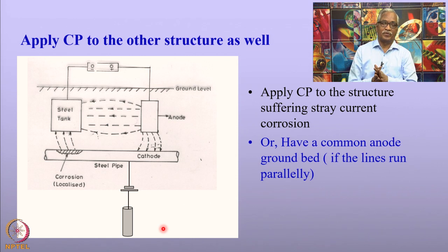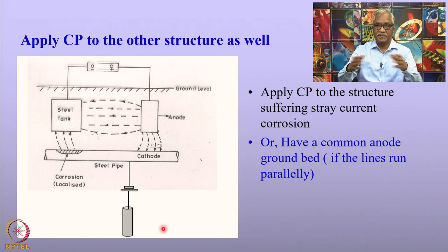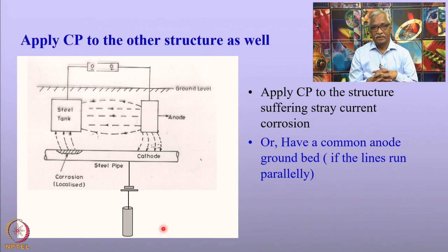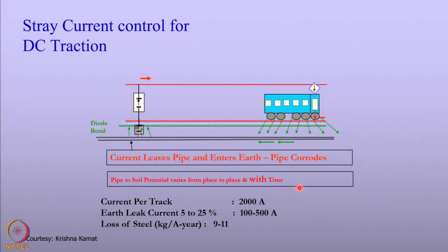Another effective way of controlling stray current corrosion is to relocate the anode ground bed. If pipelines are traveling parallel to each other, it is possible to relocate the anode ground bed far away from the intended pipelines, making the stray current entering the foreign line minimal. We have seen earlier that stray current corrosion in the DC traction system is very severe and requires control to prevent rapid corrosion. This is done using almost all the principles discussed so far.